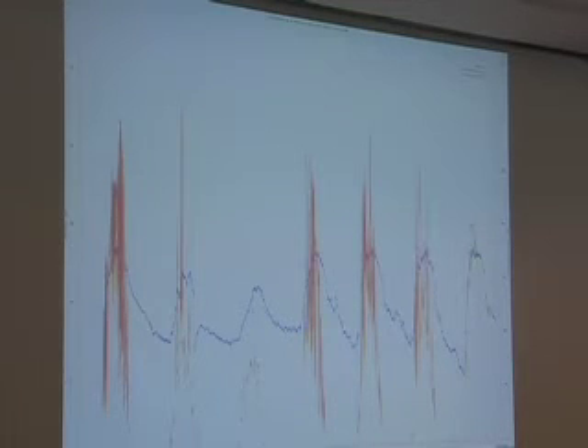And the other thing is you need to provide spinning reserve. And when you've got loads at around 600 kilowatts during the middle of summer, if you have 300 drop off, you need to be able to catch that. And the step load capabilities of the diesel generators weren't able to catch that full step. And with the power store rated at 500 kilowatts, it gave us that functionality. One other thing to notice is on day 3, there wasn't a lot of solar at all. So I know people are pushing for the whole renewable thing, but in applications such as these where there's no wind resource and the solar is intermittent, you do need that diesel background.